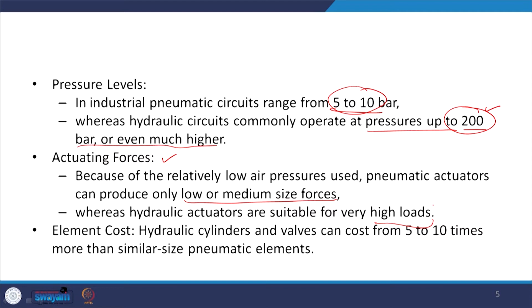Now, actuating forces. Because of the relatively low air pressure used, pneumatic actuators can produce only low or medium size forces, whereas hydraulic actuators are used for very high loads. And if we look at how they differ cost wise, hydraulic cylinders and valves can cost you, say, 5 to 10 times more than similar pneumatic elements.